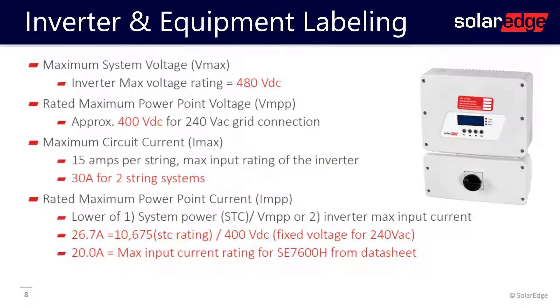The IMAX takes a little bit of calculation. Because the optimizer can output up to 15 amps but no more, we need to account for how many strings we're putting inside the inverter. In this example, we have two strings, so our IMAX is going to be listed as 30 amps.